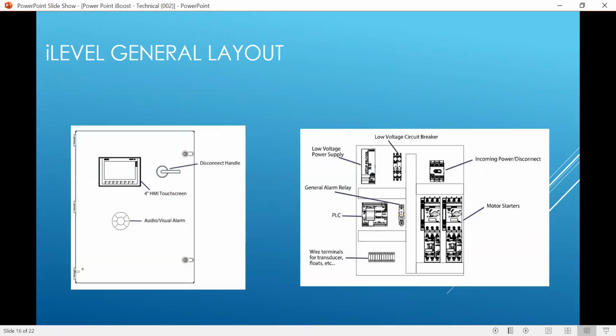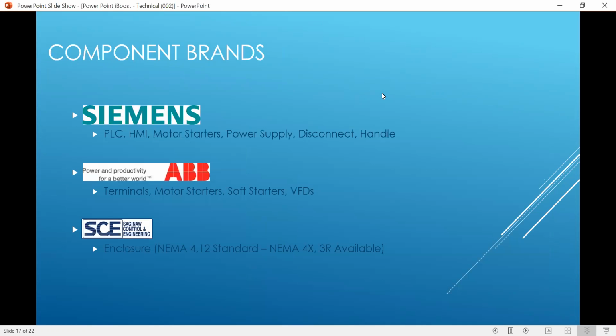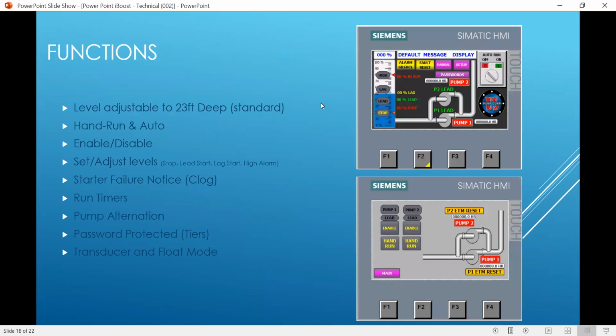As you can see, it's got standard components pretty similar to a booster system, other than it's got motor starters instead of drives. You still have your 4-inch HMI touchscreen, and you can do all your setting controls right from the touchscreen itself. Same component brands: we're using a Siemens PLC and HMI, and if necessary an ABB drive, but we're using the motor starters most times. And then the Saginaw metal enclosure. The metal is a bit of an upgrade, but it lasts longer than plastic. I don't know if you've ever seen some of the plastic sump and sewage controls, but they're pretty flimsy. We feel this is a better situation for a larger building.